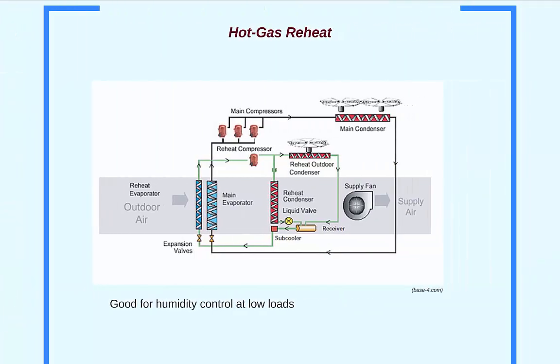Another design available is called hot gas reheat. Similar name, but a different purpose than hot gas bypass. In this design, after leaving the compressor, hot gas is routed to an additional heat exchanger placed downstream of the evaporator. This design is useful in cool, humid environments where humidity control is a concern, but the temperature of the air doesn't need to be cooled.